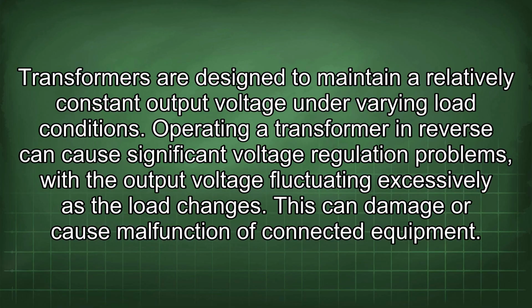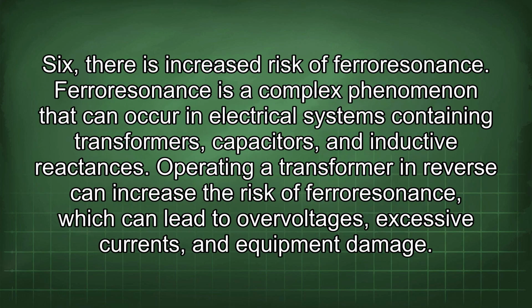This can damage or cause malfunction of connected equipment. 6. There is increased risk of ferroresonance. Ferroresonance is a complex phenomenon that can occur in electrical systems containing transformers, capacitors, and inductive reactances. Operating a transformer in reverse can increase the risk of ferroresonance, which can lead to overvoltages, excessive currents, and equipment damage.